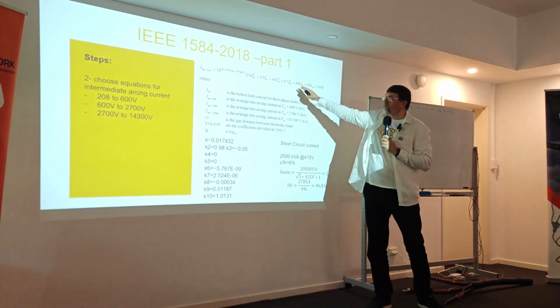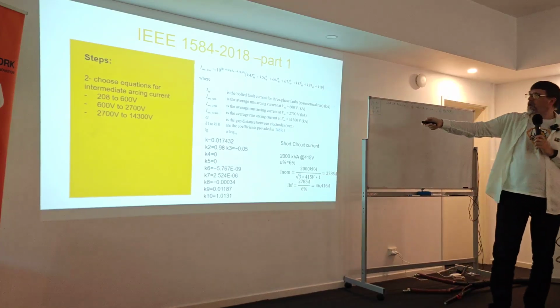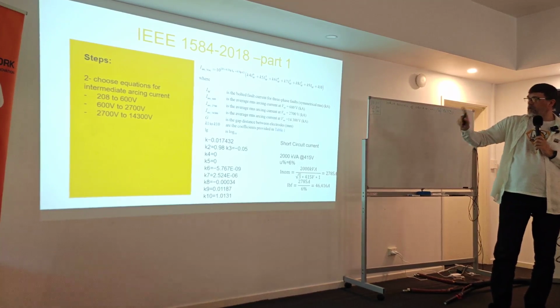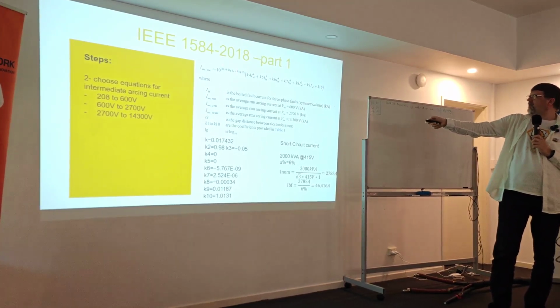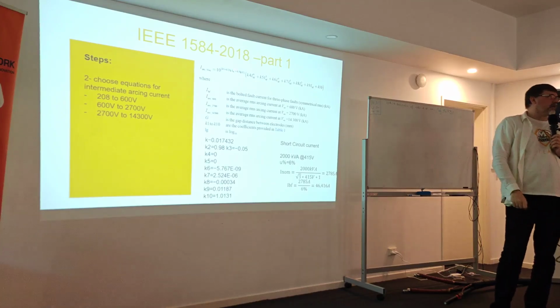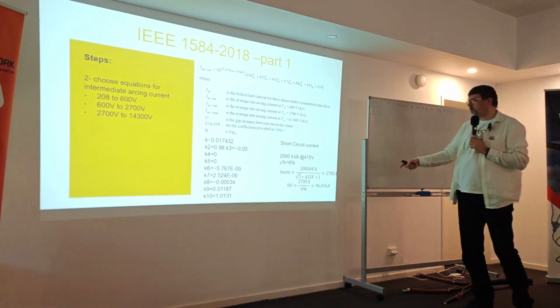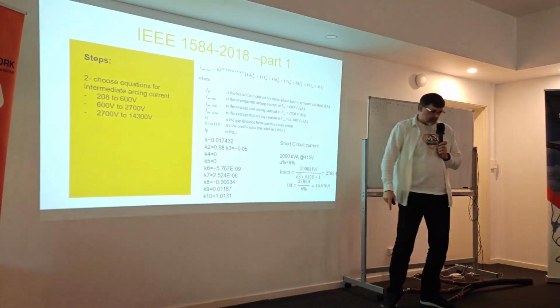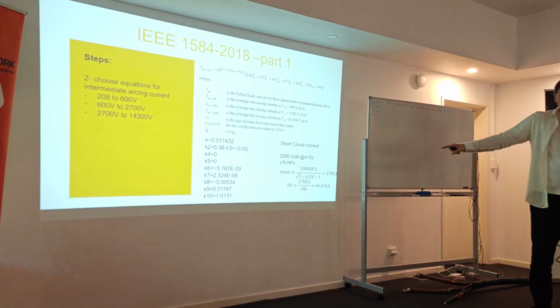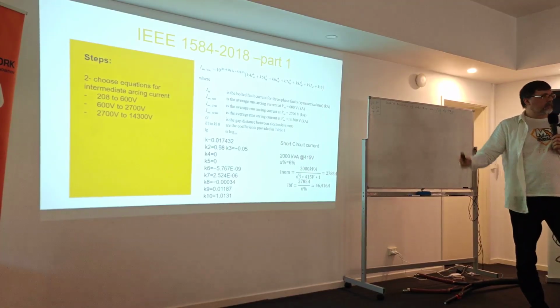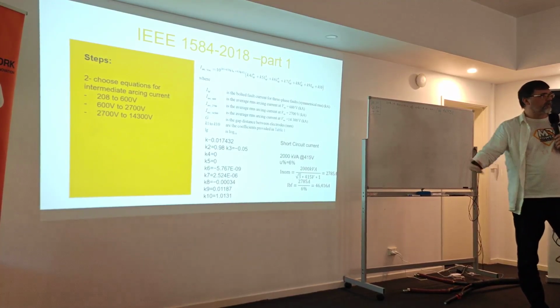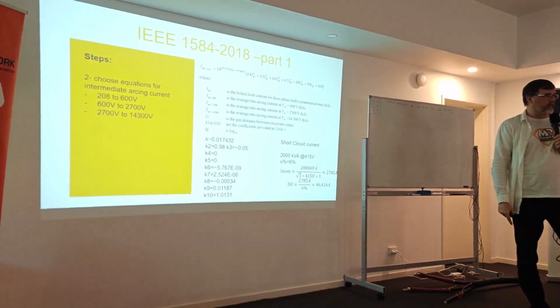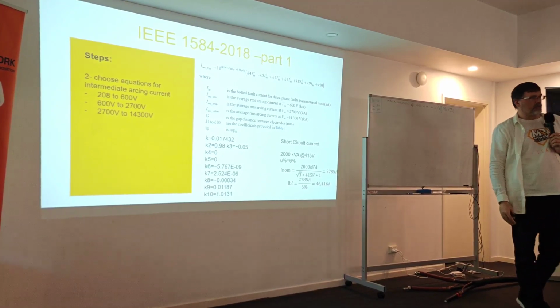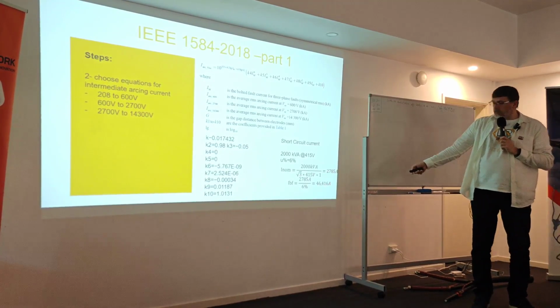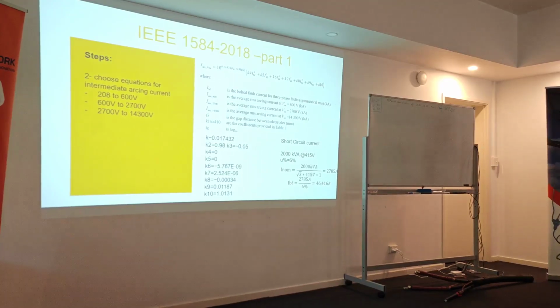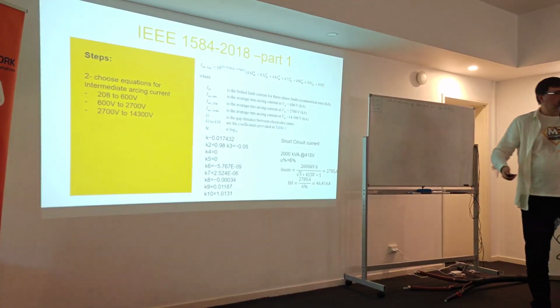We have the coefficients, which was the table I showed you before, but we also need a few other things. We need the gap between the electrodes, which we took as the default, which is this one. And then we need the bolted fault current here. Bolted fault current, if you don't know how to get it, that's why we use the software again, but generally, if you have a transformer, let's say 2 MVA that I choose for this example, and it has a certain short circuit impedance, the easiest way to calculate it is like this. Technically, nominal current divided by the short circuit impedance will give you the short circuit current, the worst case short circuit current on the transformer, assuming there is nothing else, no limitation, and so on. You just need to get to the nominal current, and from the nominal current to the short circuit current, so we expect 46 kiloamp, 46.4. That's what I need to make my calculations.